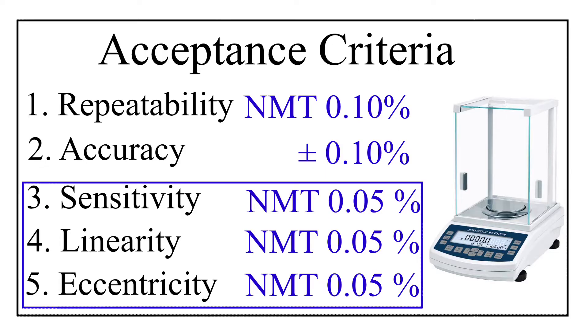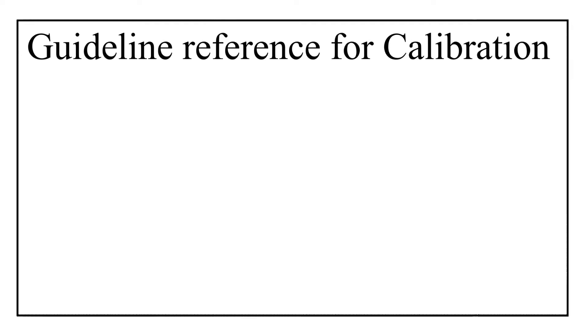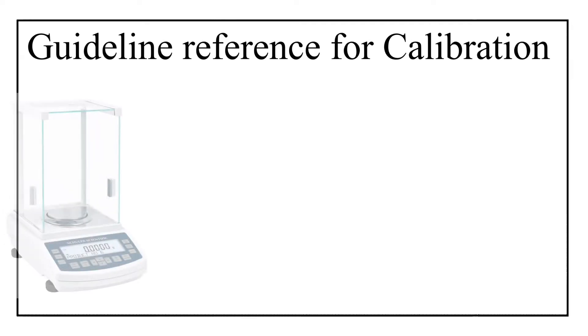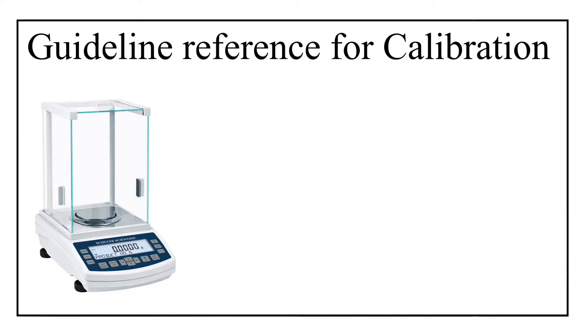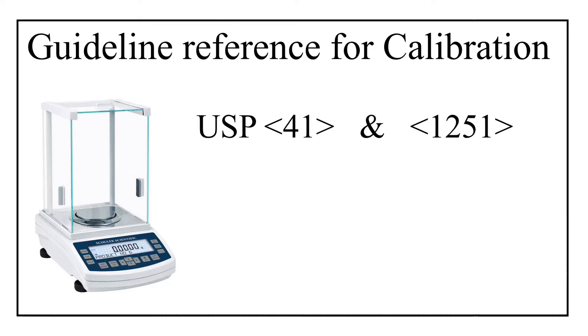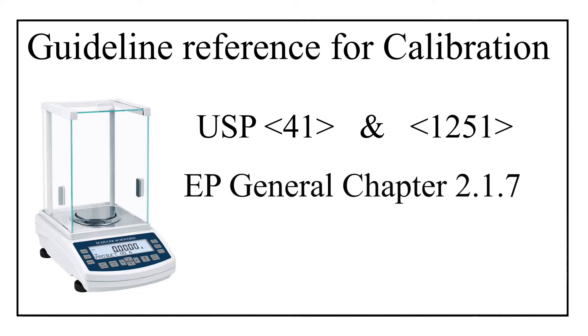Now, the last learning of today's video: which guideline should we refer to for balance calibration? The answer is U.S. Pharmacopoeia general chapters number 41 and 1251. Along with that, you can also refer to European Pharmacopoeia general chapter number 2.1.7.